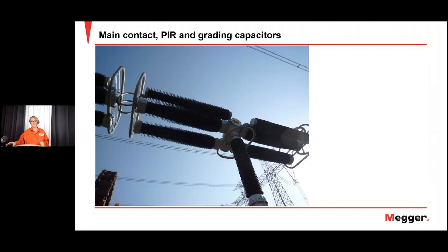So here you can see a close-up on this same breaker, the 800 kV, and you can see here the PIR, which needs a mechanism, right, to be able to operate. Grading capacitances, which is here, is directly connected without any mechanism, because it's connected there the whole time. And you have the main contact in the middle.